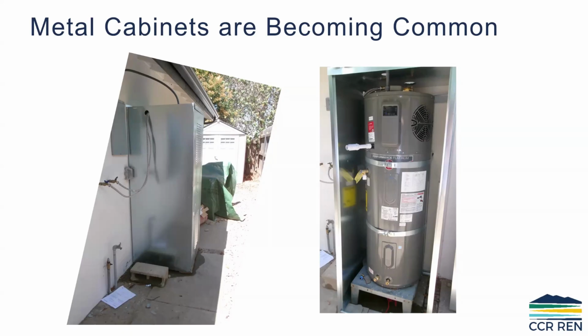We had a project here in County of Monterey where they did a stackable pre-manufactured housing apartment building, and they stuck heat pump water heaters in a conventional water heater closet with conventional water heater combustion air ductwork, just blowing the air right into the closet itself with the louvers acting as combustion air. The rooms sweated so badly they started molding.